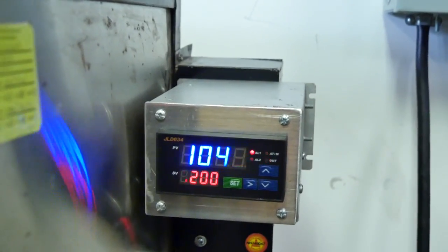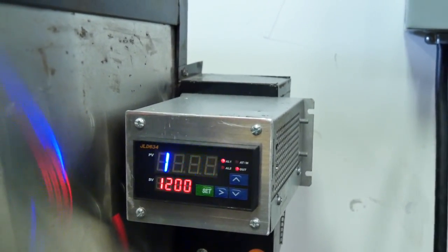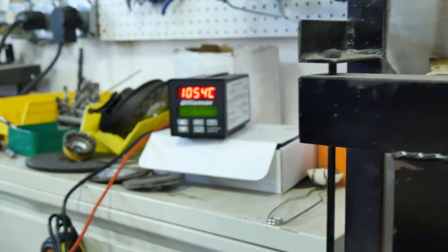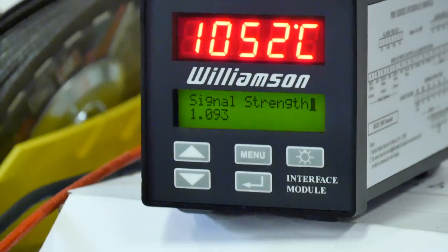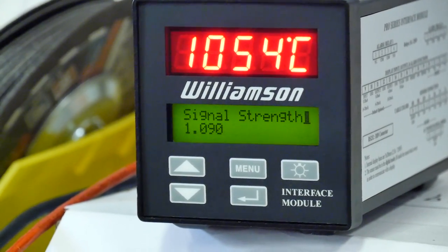So that makes a huge difference. The K-type thermocouple, which is presenting the temperature here, is saying 1047, and over here the Williamson is reading 1052. So ballpark in the same range.